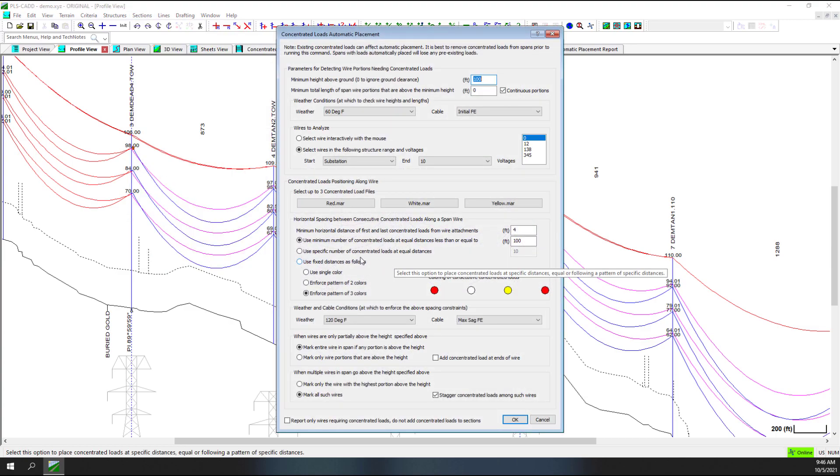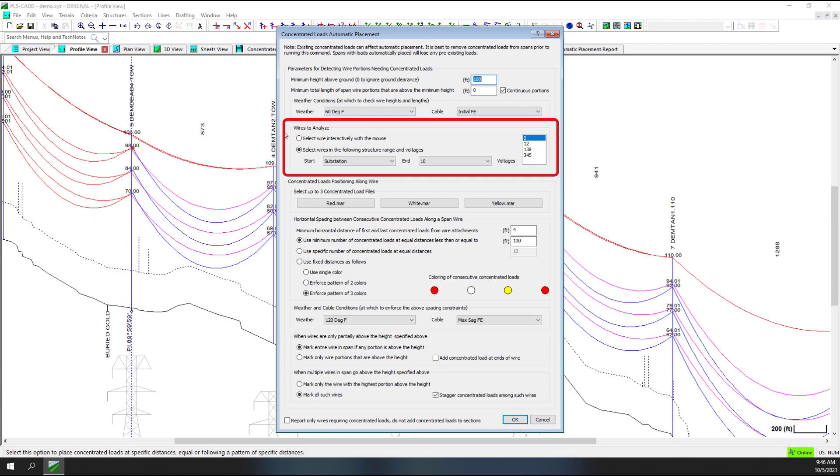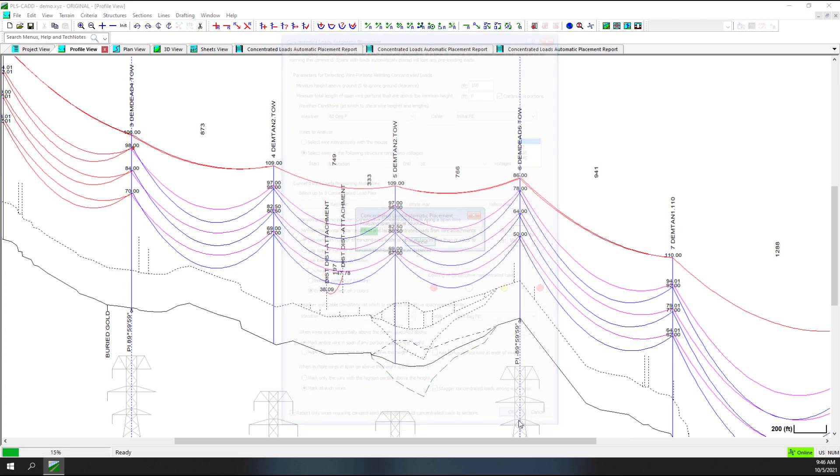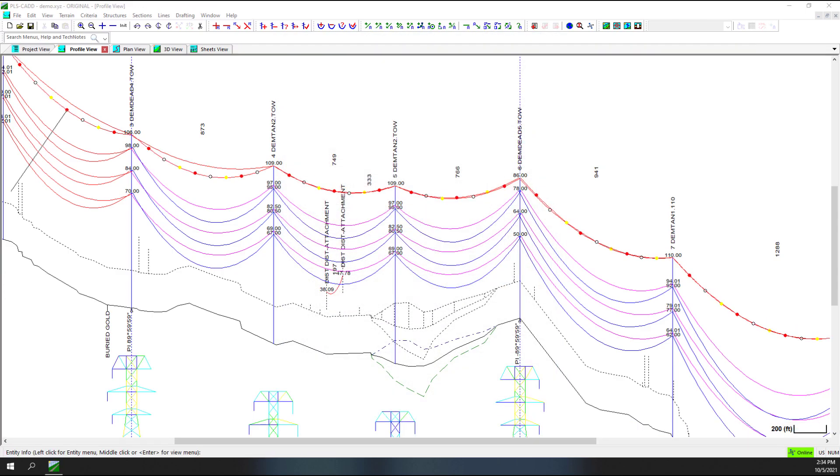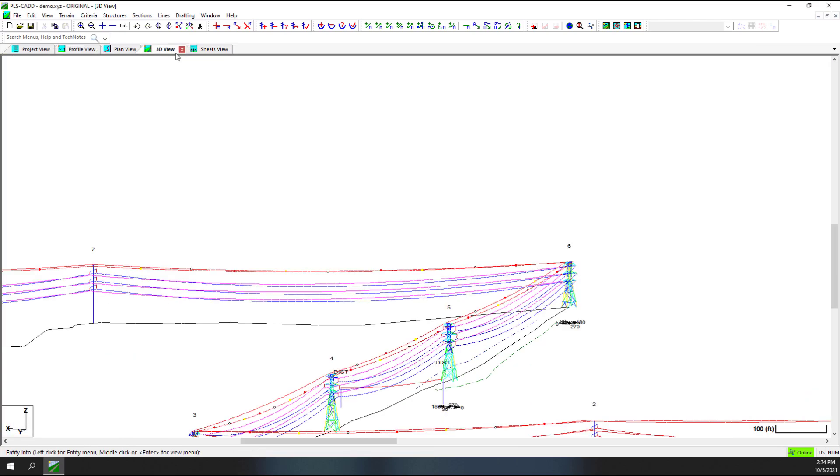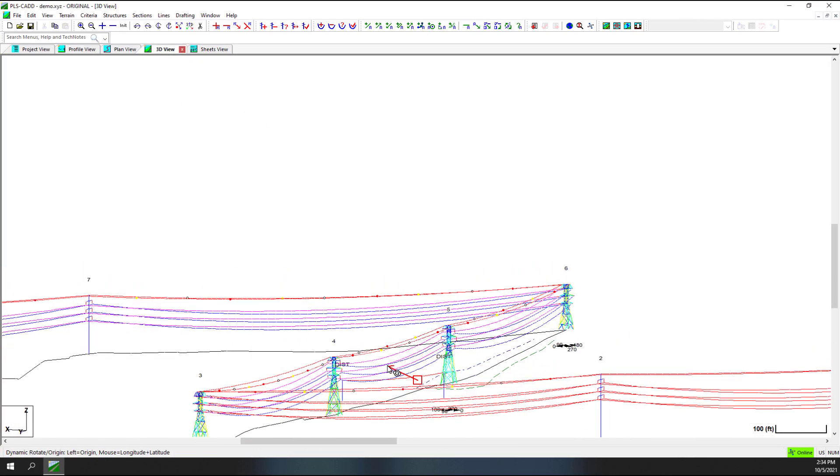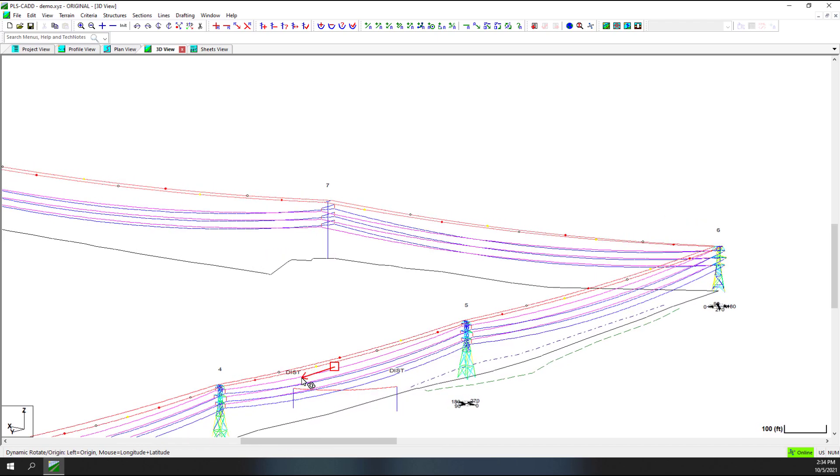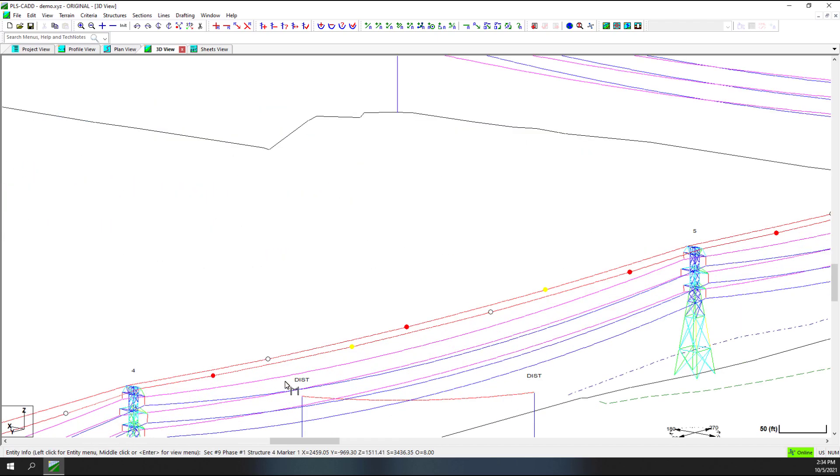Designate the height above ground and weather conditions to be used in placing the concentrated load as well as the range of structures or the voltage to apply. Select up to three concentrated load files and specify your spacing requirements. Click OK and watch as the program automatically places your concentrated loads. See Appendix N.5 of the PLS-CADD User's Manual for more information on the use of the Concentrated Load Automatic Placement feature.